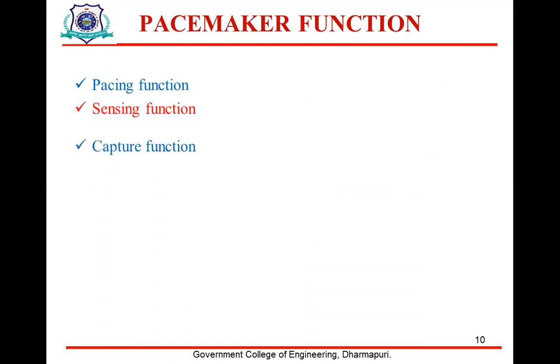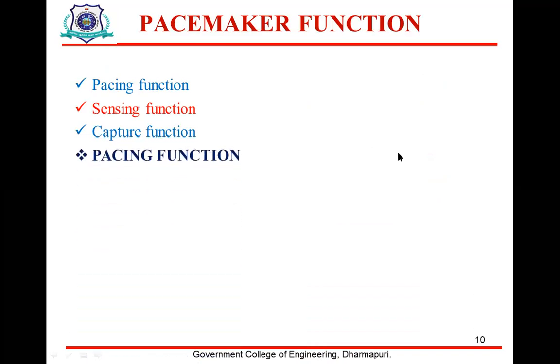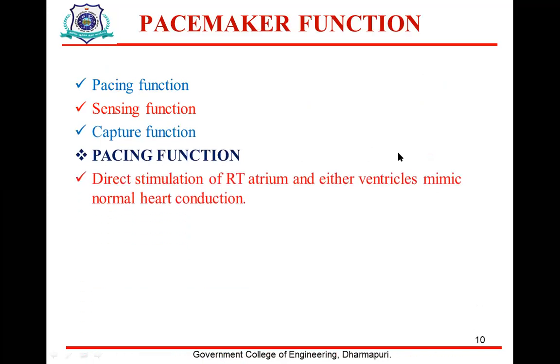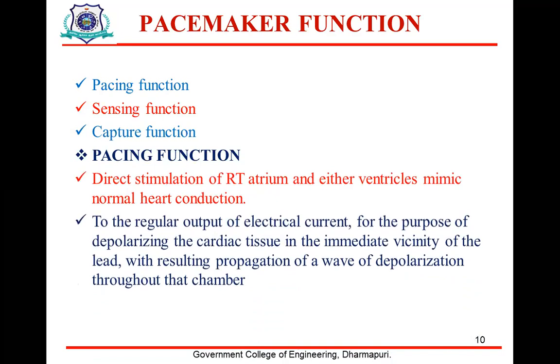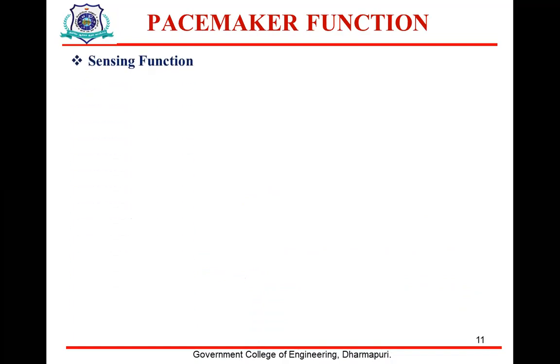Pacemaker function. You will see the pacemaker function. It has three functions: pacing function, sensing function, and capture function. What does pacing function mean? In pacing function, direct stimulation of the atrium or ventricles mimics the normal heart conduction. It regulates the output of electrical current for the purpose of depolarization of the cardiac tissue in the immediate vicinity of the lead, with the resulting propagation of a wave of depolarization throughout the chamber.